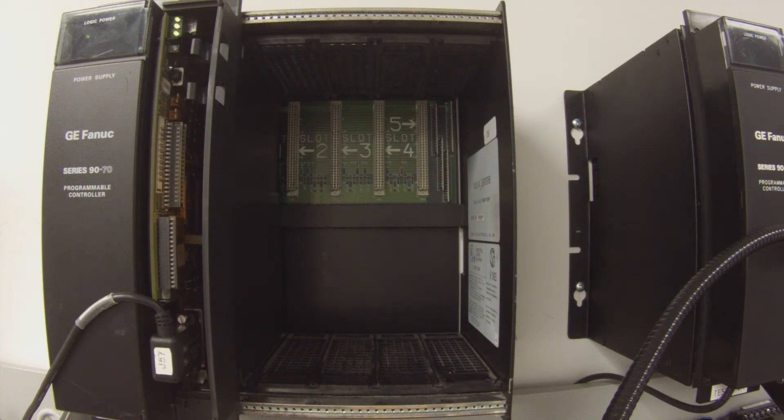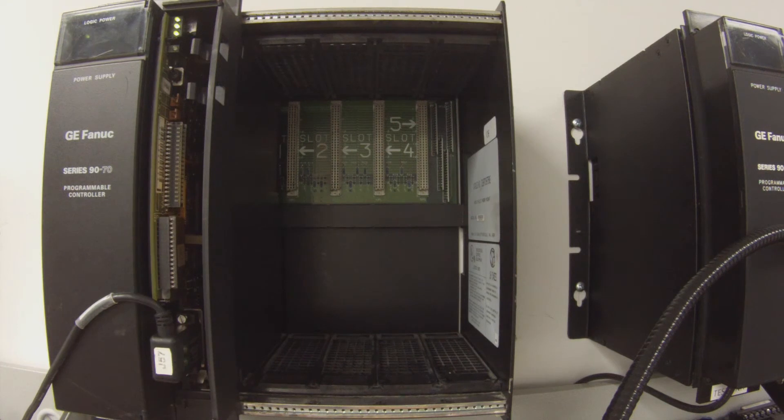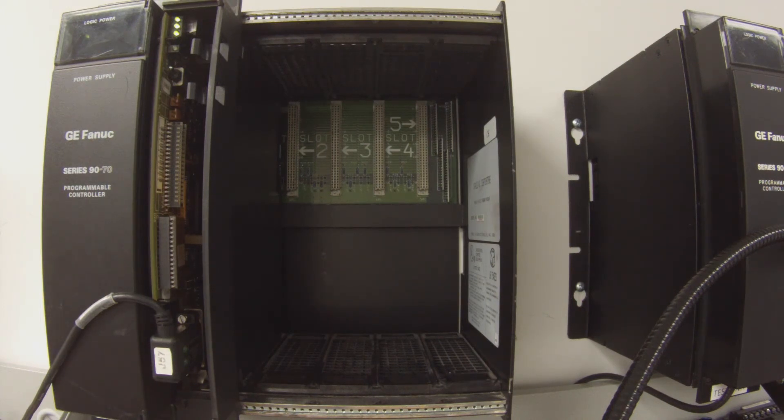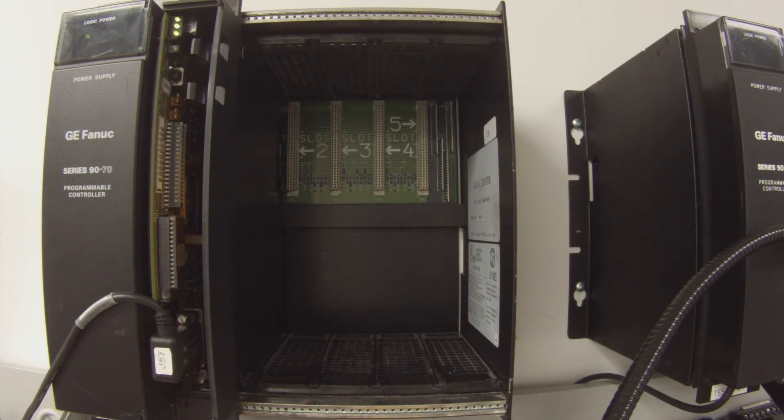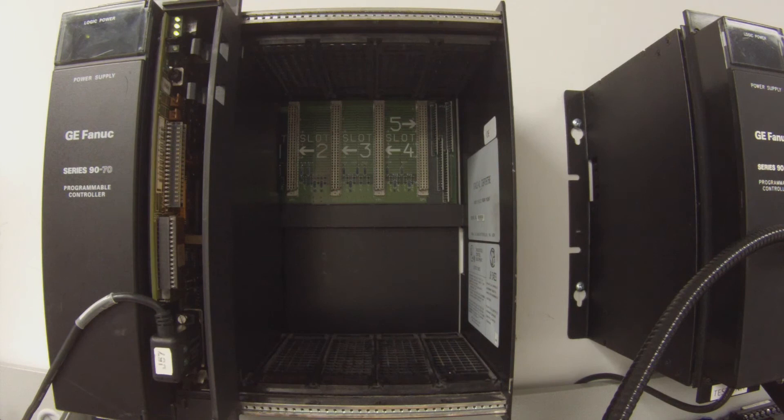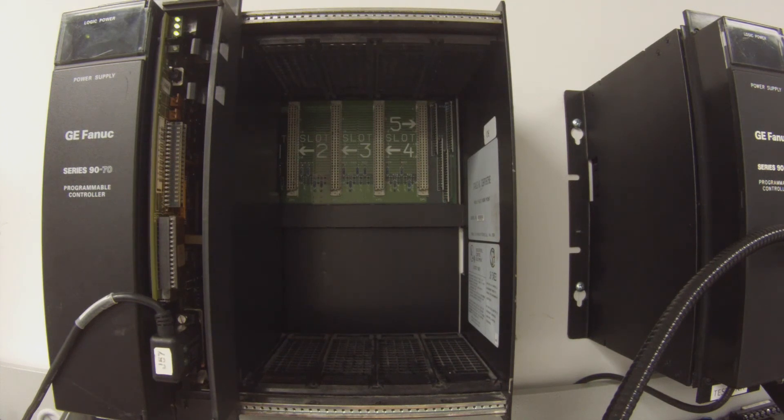What I would recommend is you go to Proficy Machine Edition while you are still connected and go to your target in the top menu bar and then go down to diagnostics. Click on diagnostics and your info viewer screen will pop up with a fault table and it will tell you exactly why it popped out of run mode. It will give you the errors. Sometimes the errors, depending if you click on them, they may be written in codes and be hard to understand. A lot of times we do get very useful information from it so I do recommend that you check there if you have a problem.